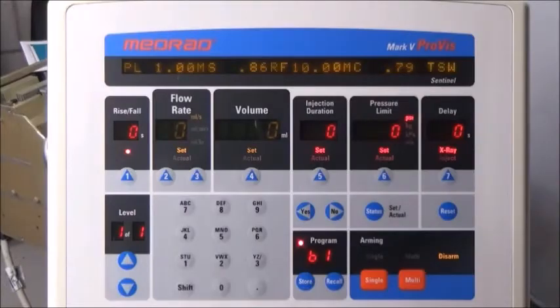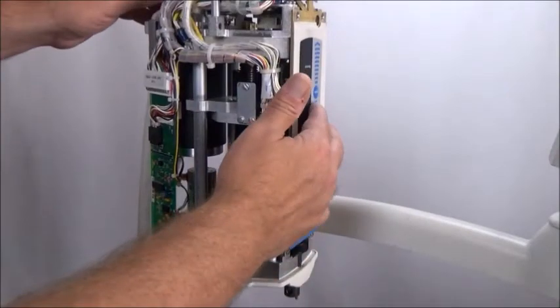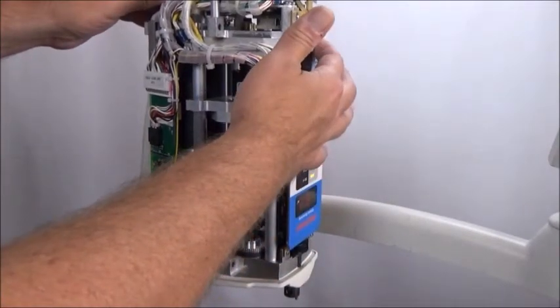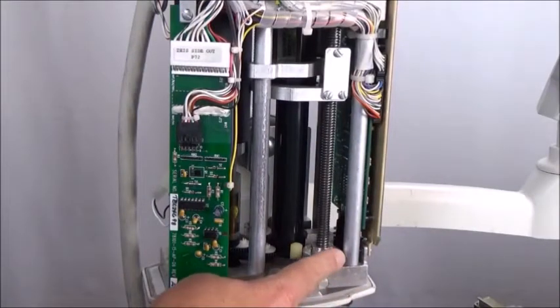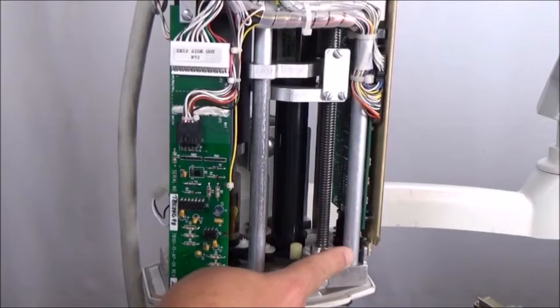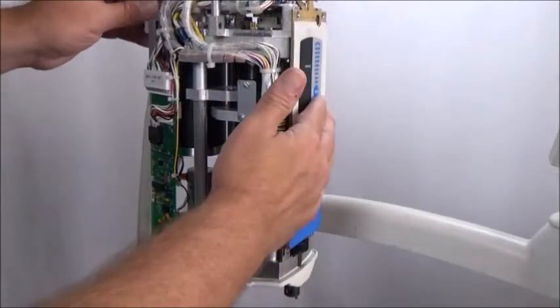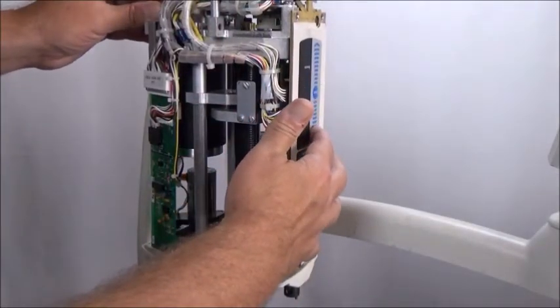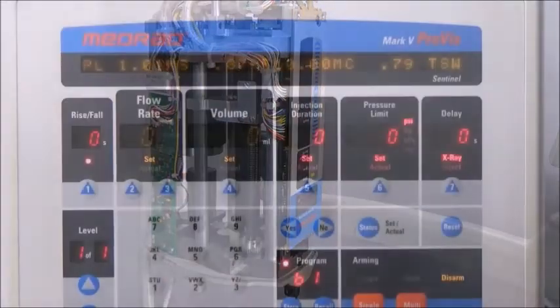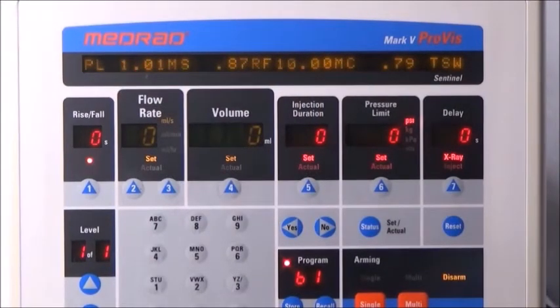If the reading is off, fully retract the piston with the reverse button on the injector head, readjust the position of the MS plate, backward to decrease the voltage, forward to increase the voltage, then drive the plunger plate into the MS plate again and check your PL voltage. Repeat this procedure until you get a PL rating of 1.01 volts DC with the two plates impacted.